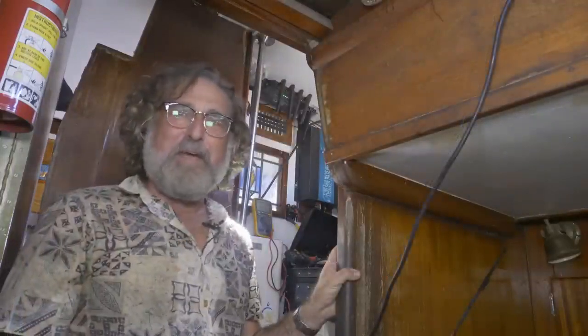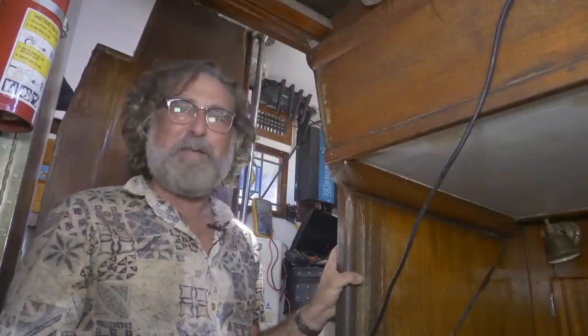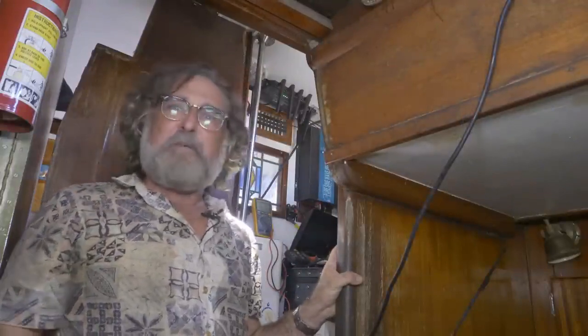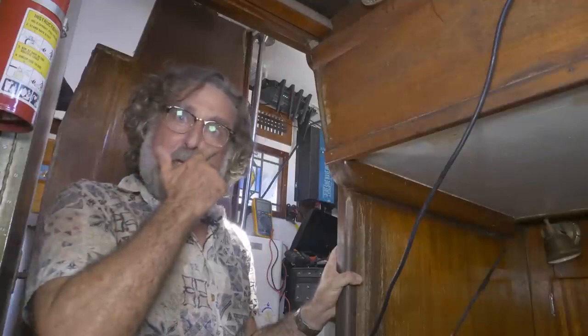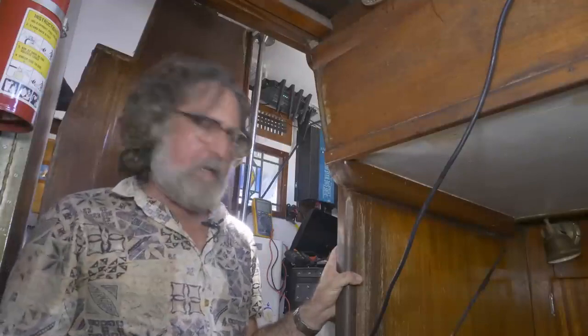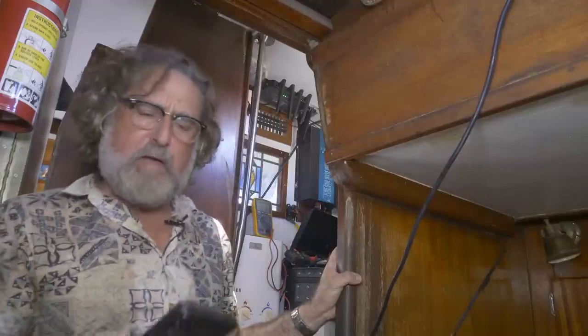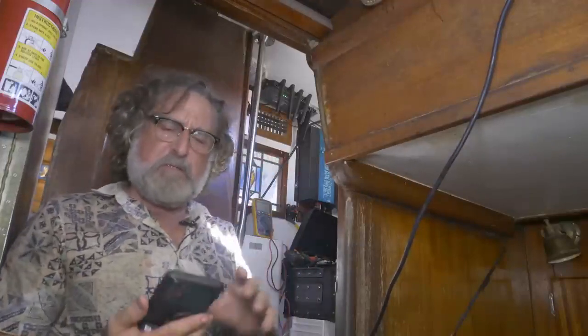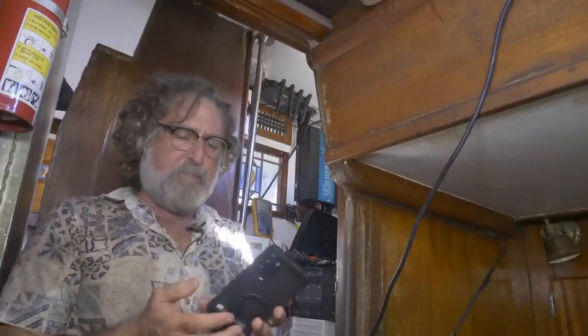That screeching is my inverter. It overheated. We're going to have to bring this test down a notch, but we got 8 minutes out of the battery, putting out 3,000 watts. That's pretty close to its rating. Let's take a quick look with the temperature probe.